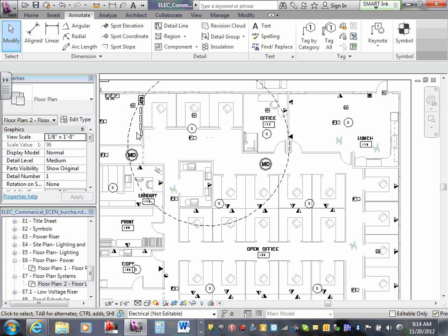Horns, obviously, they're usually pretty loud. But you can pick different candelas to have different coverages. Some fire alarm installers will tell you that it's better to have two or three 75s rather than one 110, because depending on where you're standing, you might not catch it out of the corner of your eye if it has a coverage that's behind you. If you have the coverage with the 110, you're meeting the requirements. But sometimes using the smaller ones and more of them is just better practice.